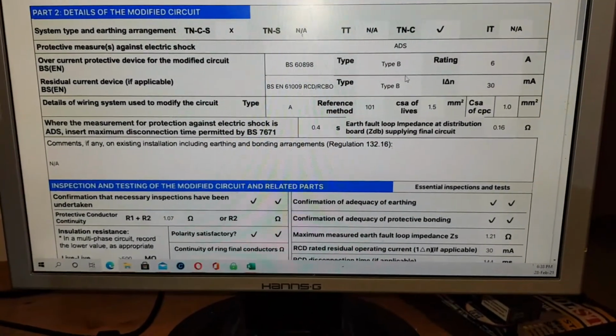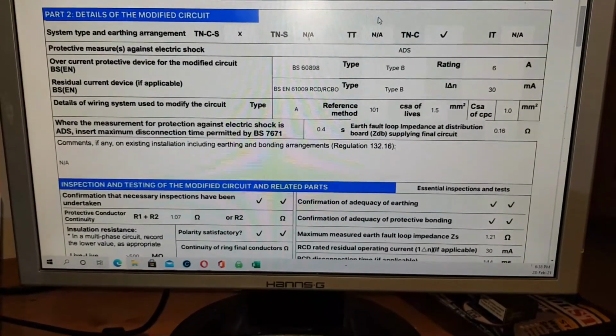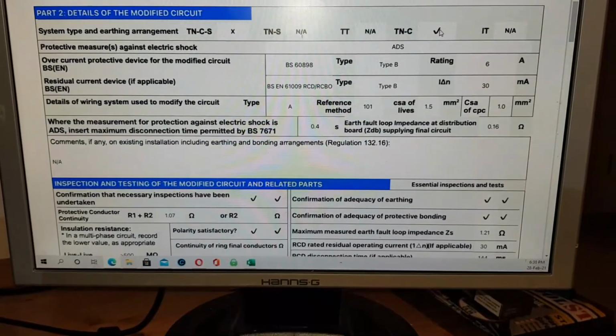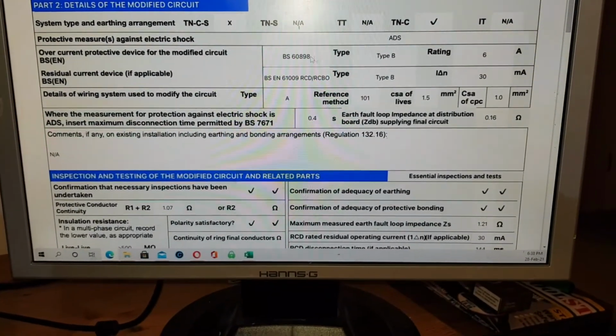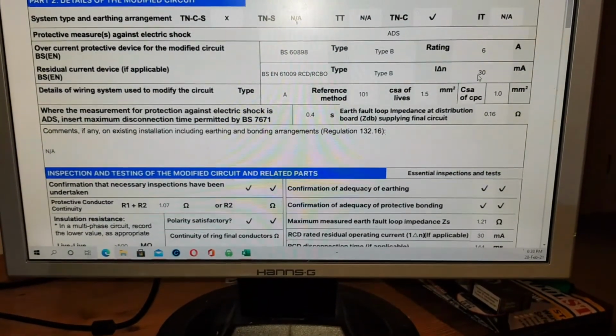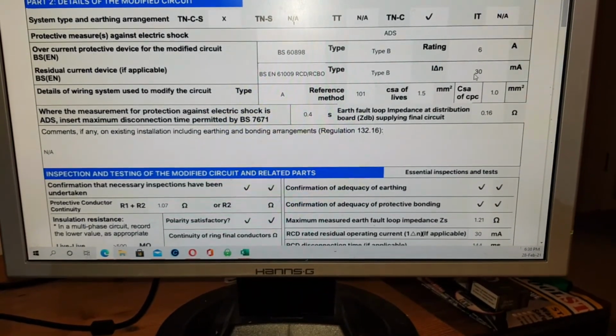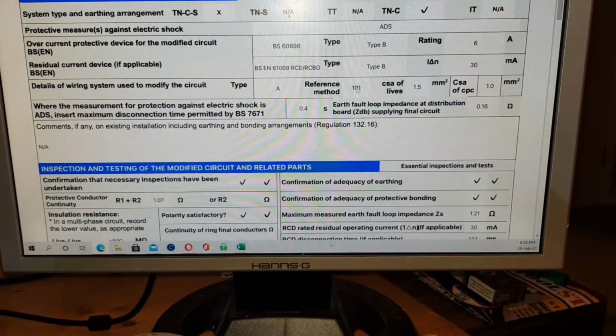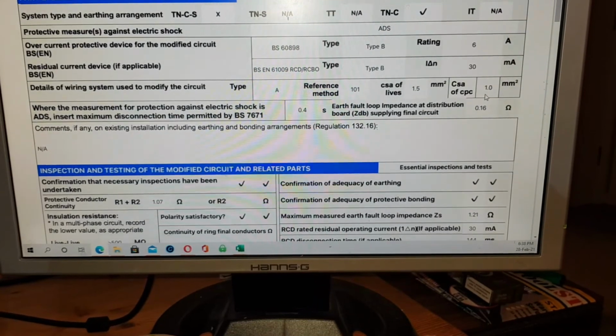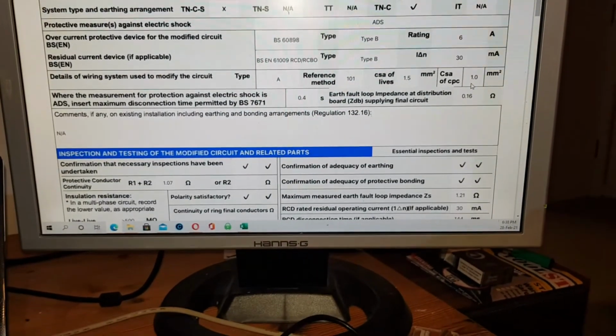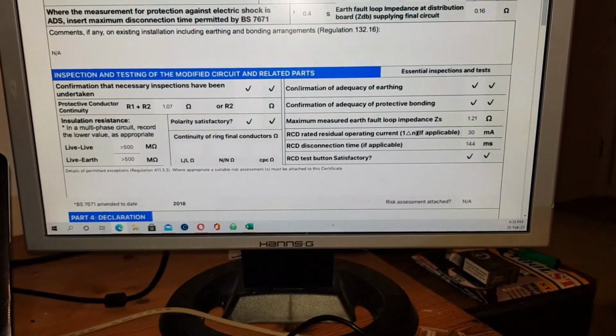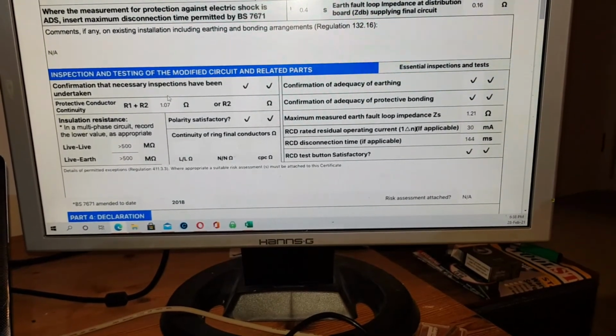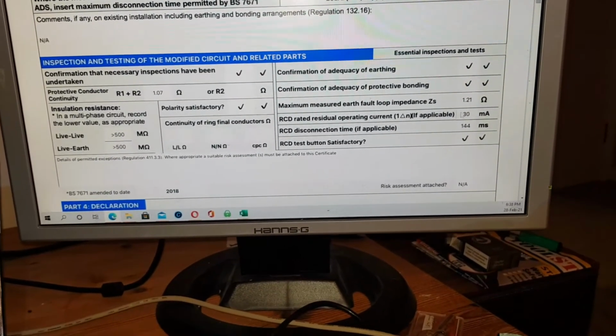And here we have the minor work certificate all filled out because the testing was fine. So that's a TNC system with a 6 amp circuit breaker and protected by a 30 milliamp RCD. Circuit conductors are 1.5 twin and earth with a 1mm CPC. Done the R1 plus R2, absolutely fine. It's going to pass no problem.